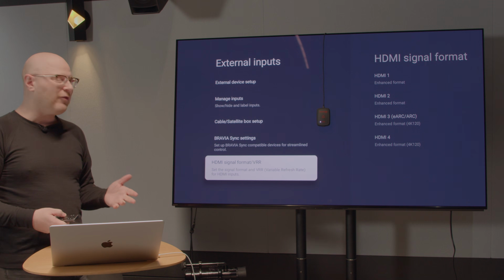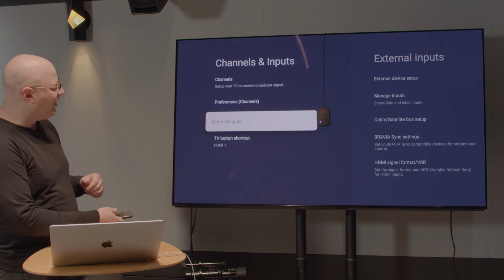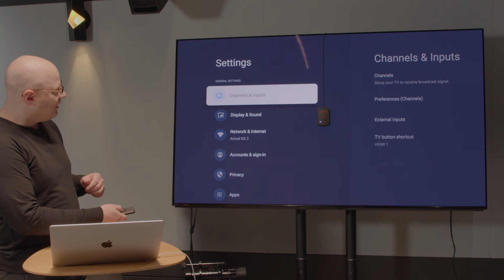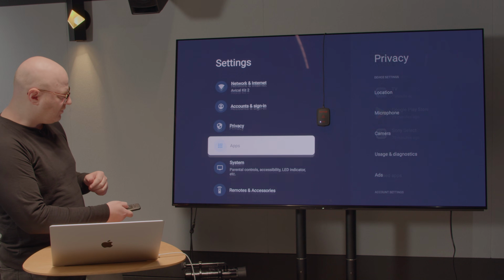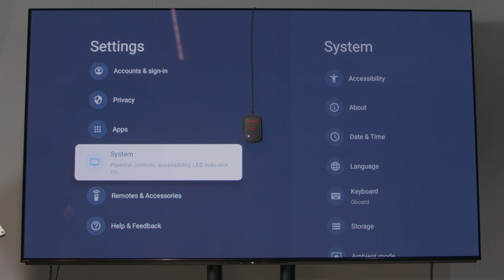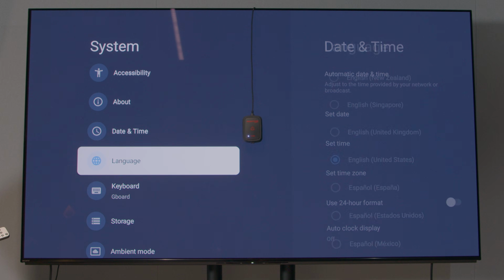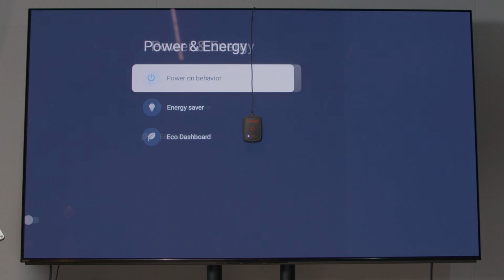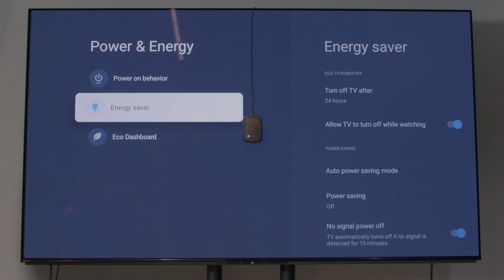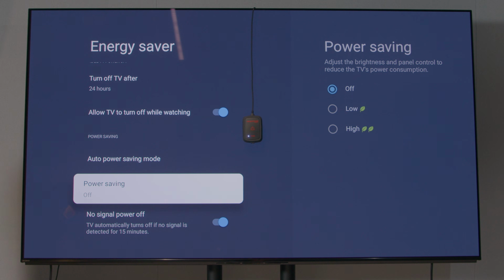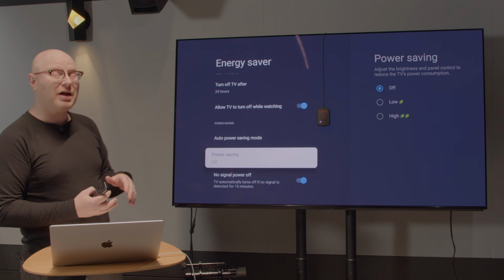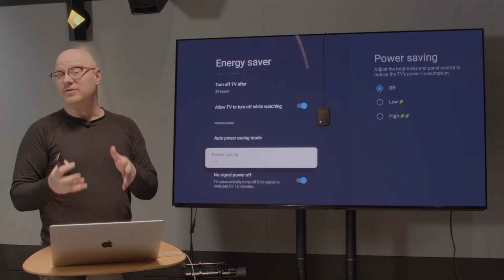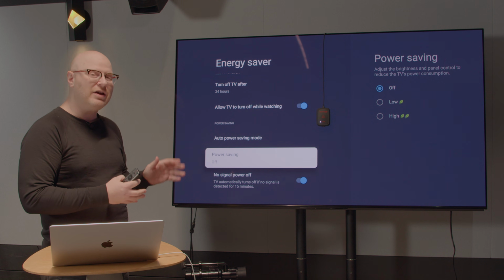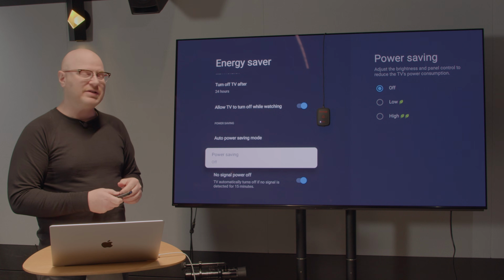Okay, now that we have our HDMI input set, we'll press the back button and we'll come down to System. Click on System and scroll down to Power and Energy. Here, we're going to want to select the energy saver and make sure that the power saving is set to off for the calibration process. If you'd like to turn it on after the calibration process, you may do so, but we don't want any energy saving affecting the calibration measurements as we're making them.